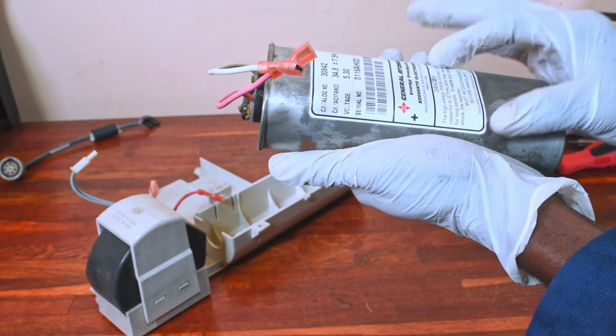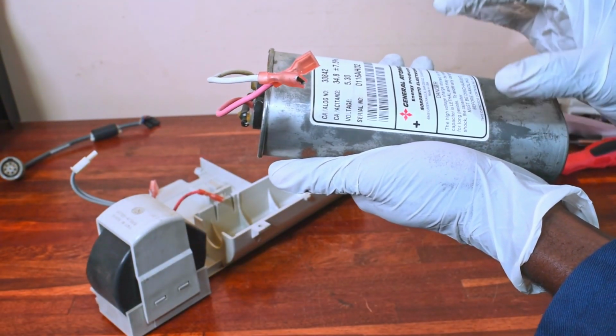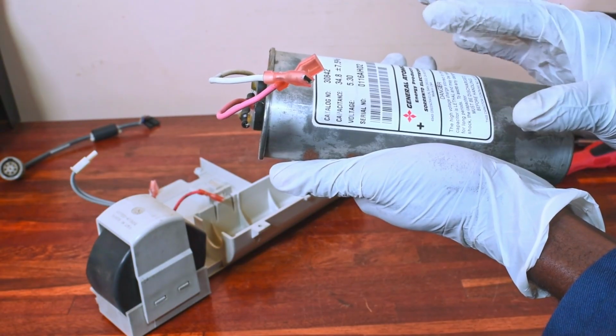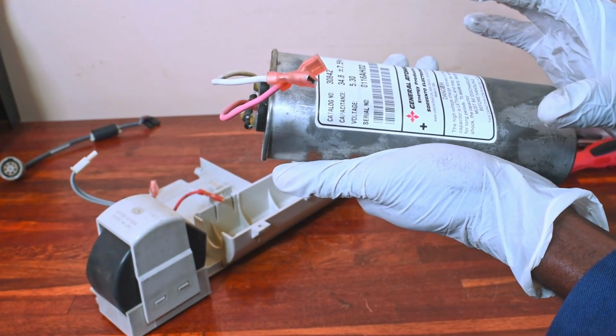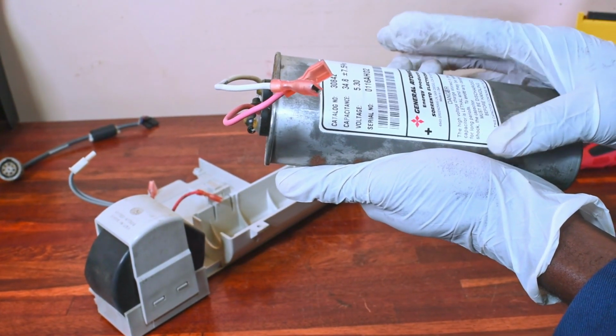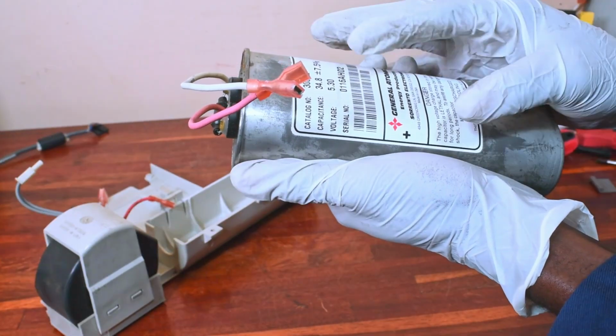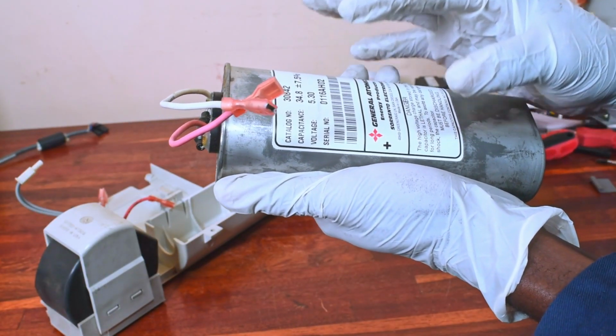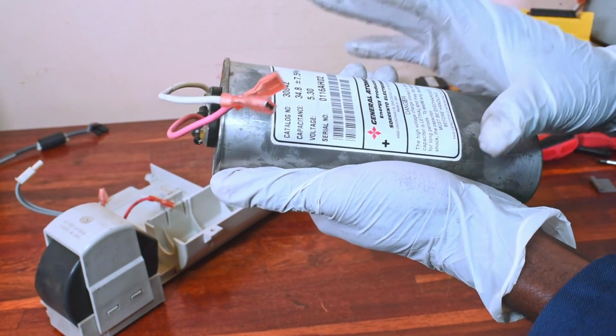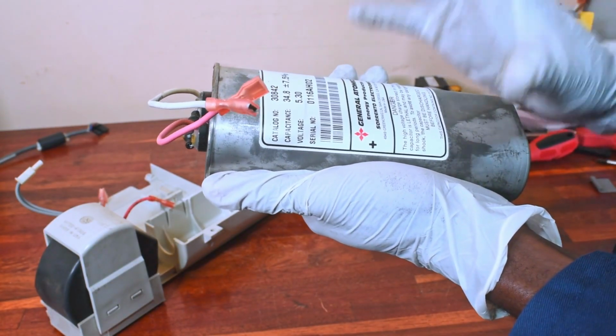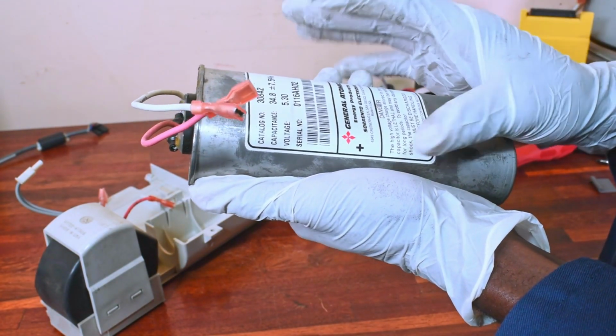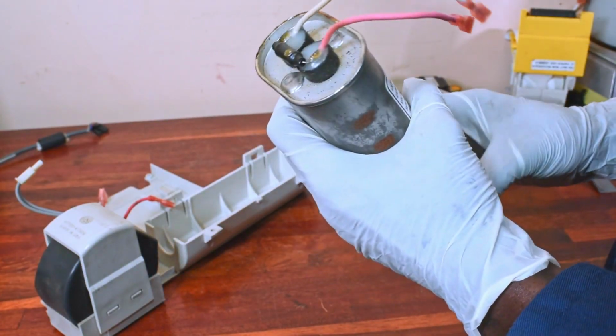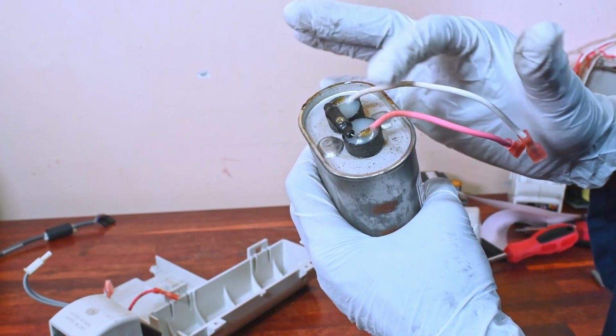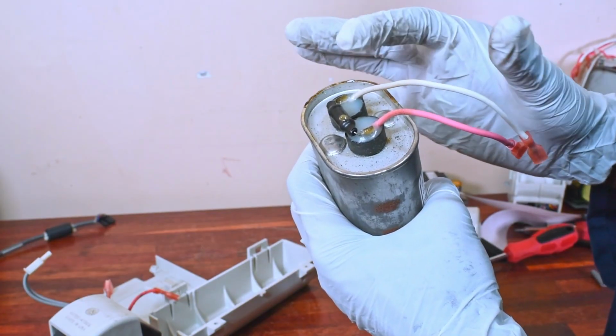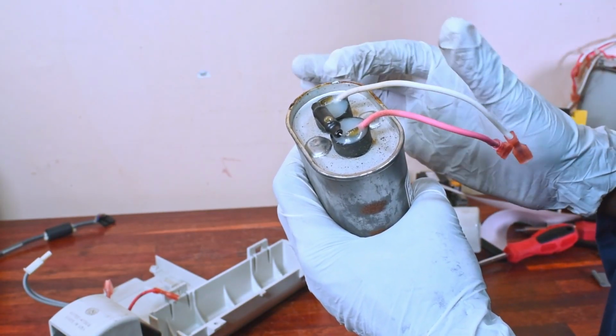This is the high voltage capacitor. This capacitor has a capacitance rating of 34.8 microfarads with a tolerance of plus or minus 7.5%. It has a voltage rating of 5.3 kilovolts. As earlier mentioned, make sure that this capacitor is discharged before you touch it. And you can discharge this capacitor by shorting these two terminals using an insulated screwdriver.